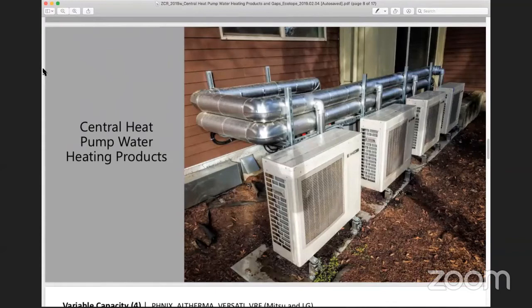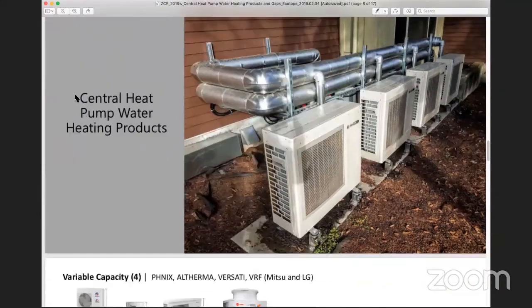So you're running essentially 15 apartments on one stand-in in terms of its compressor, right? Yeah, and then there's about 800 gallons of storage, including the swing tank. Okay, but these are almost 16,000 BTUs, and a standard tank is 4,000 BTU. So in some ways, it's as if you had a normal integrated 80-gallon tank supporting 4 apartments, which is a lot, but yeah, this seems to be in line with how single family homes work in terms of your capacity. Yeah, okay, cool. Thank you.